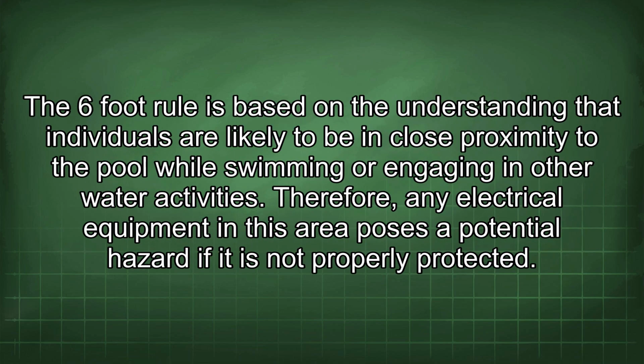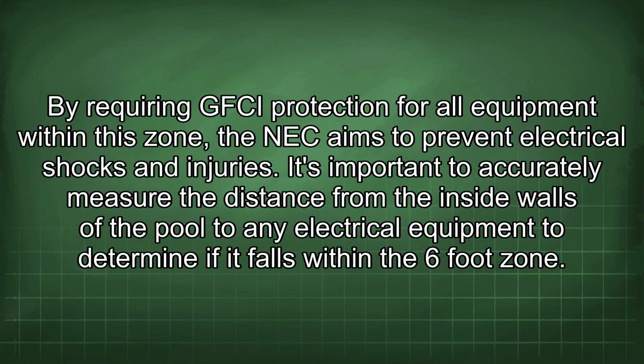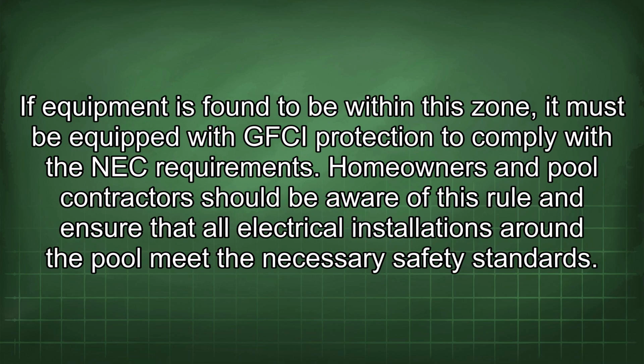This includes not only pool pumps and filters but also any lighting fixtures, receptacles, or other electrical devices. The 6-foot rule is based on the understanding that individuals are likely to be in close proximity to the pool while swimming or engaging in other water activities. Therefore, any electrical equipment in this area poses a potential hazard if it is not properly protected. By requiring GFCI protection for all equipment within this zone, the NEC aims to prevent electrical shocks and injuries. It's important to accurately measure the distance from the inside walls of the pool to any electrical equipment to determine if it falls within the 6-foot zone. If equipment is found to be within this zone, it must be equipped with GFCI protection to comply with the NEC requirements. Homeowners and pool contractors should be aware of this rule and ensure that all electrical installations around the pool meet the necessary safety standards.